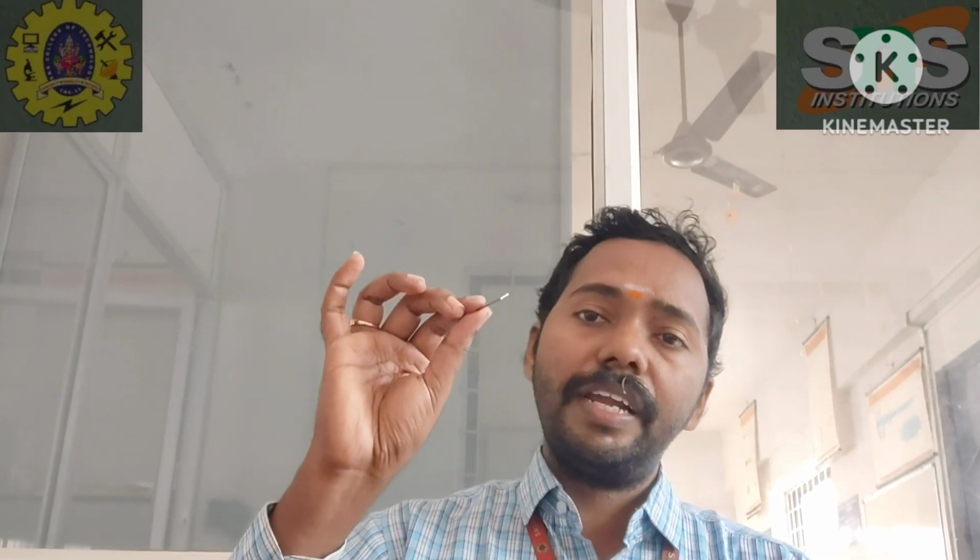This is one of the best examples, and this is the example for 1.17 mm. So this is the minute value of the slip gauges. The slip gauge is mainly carried in the slip gauge box. It is fully safe and also maintained at the proper temperature to avoid corrosion. The slip gauge is highly used with the sine bar, because you measure the height of the valley, and in the calibration process. This is a measuring gauge and checking gauge. The slip gauge is otherwise called a measuring gauge, and the second name is checking gauge.